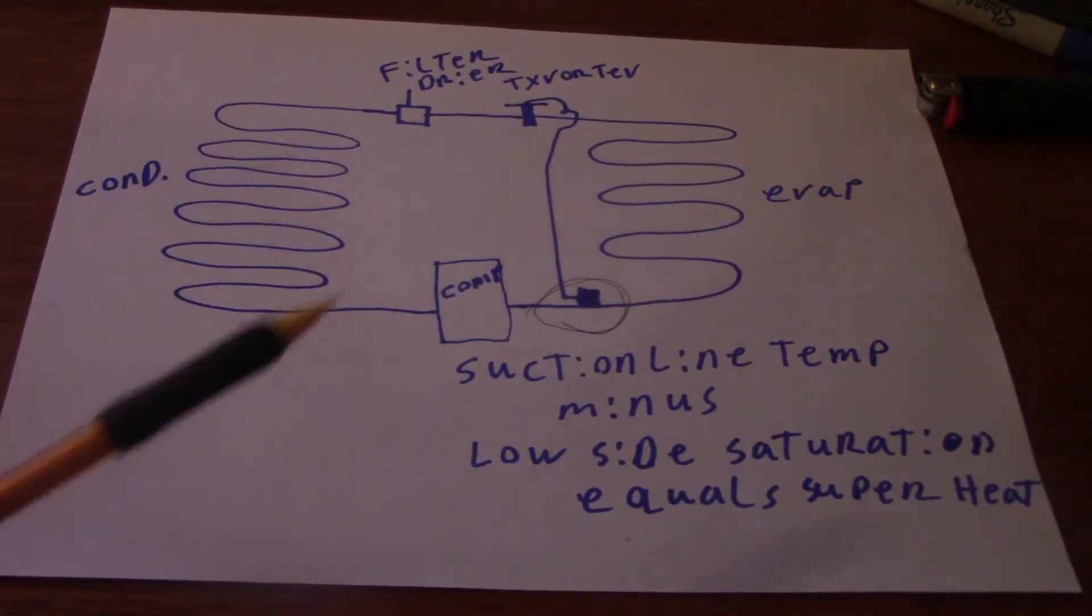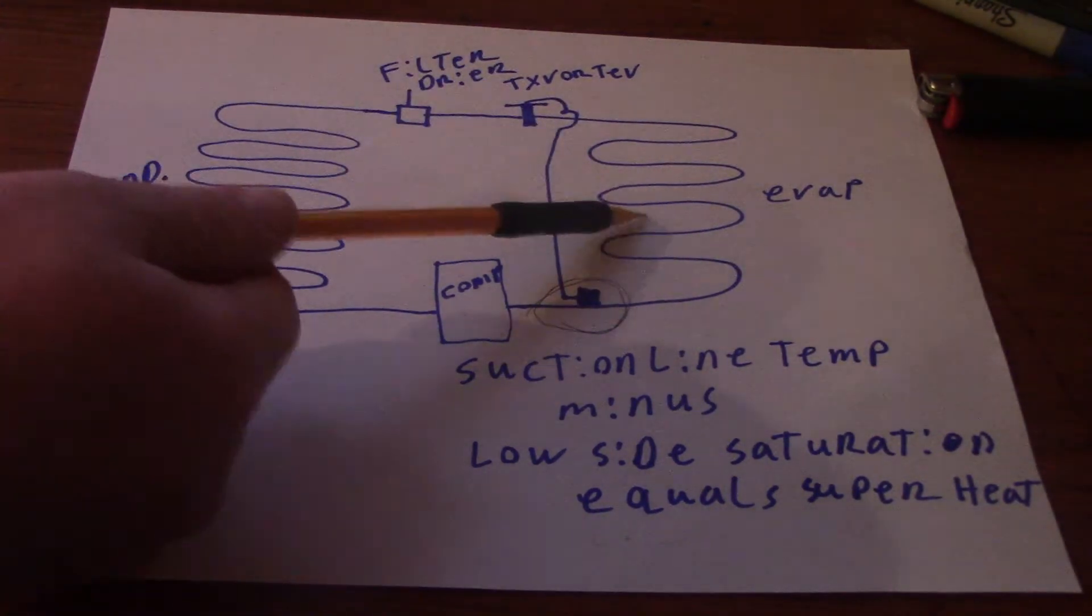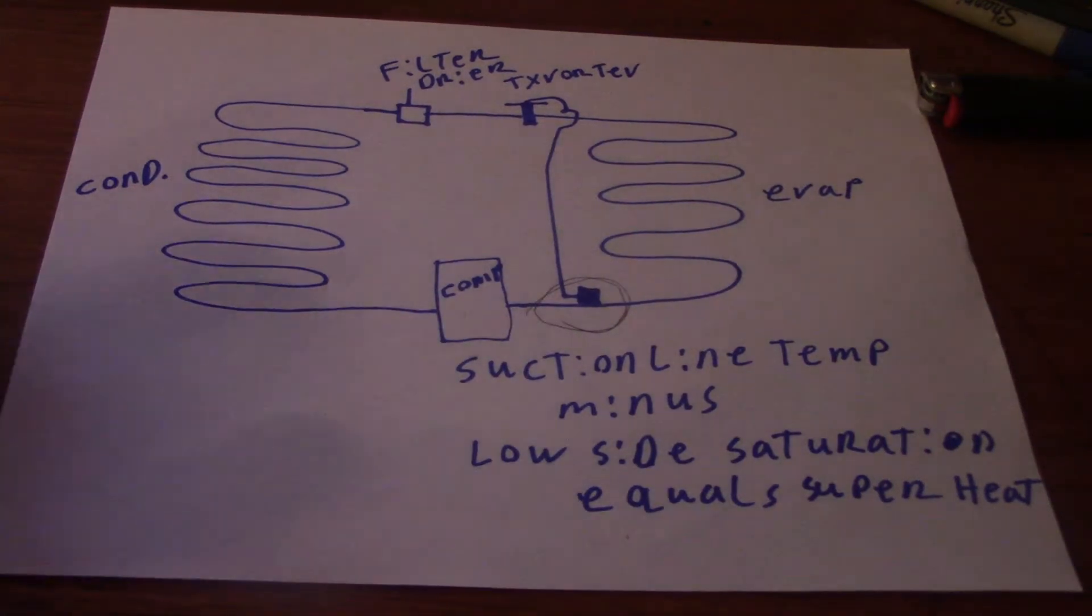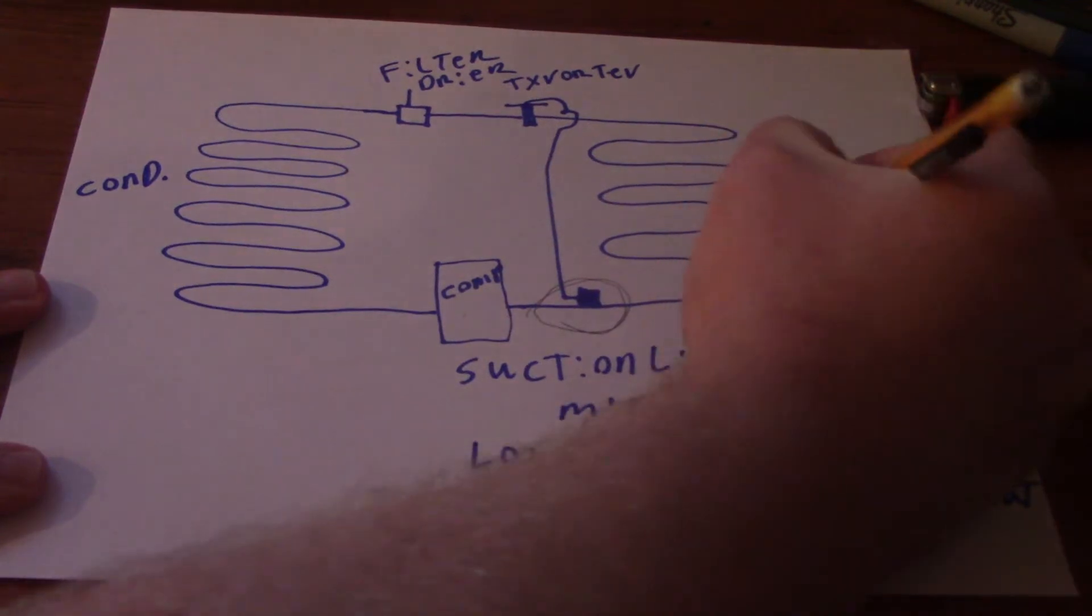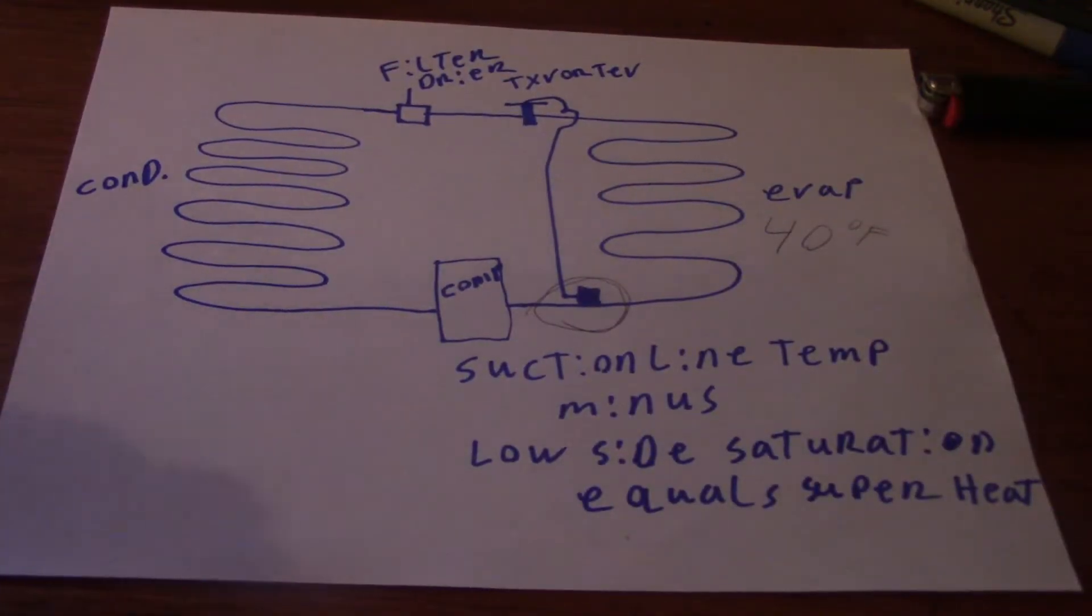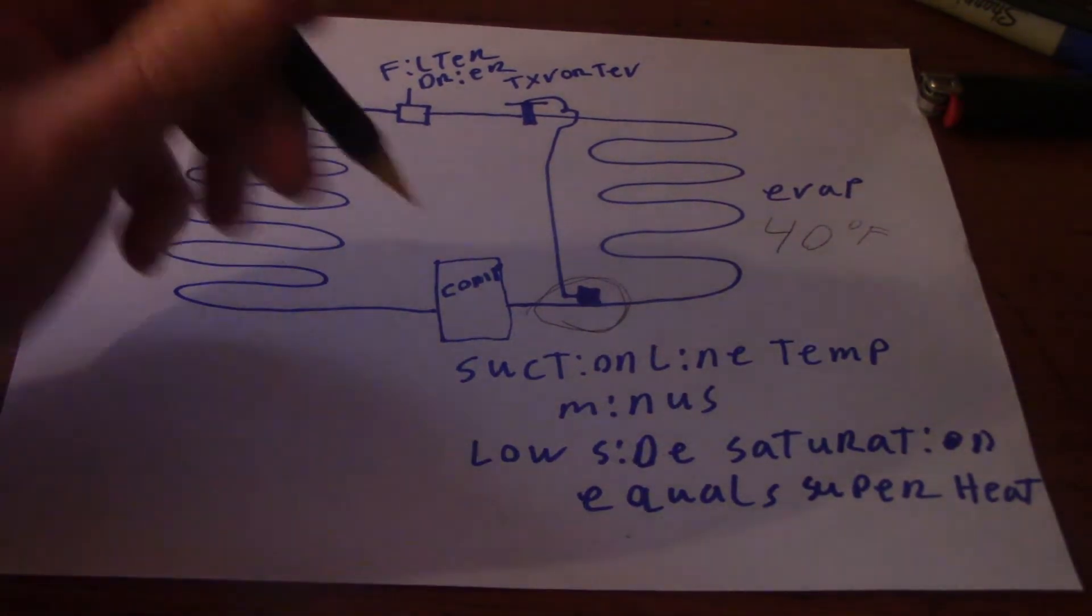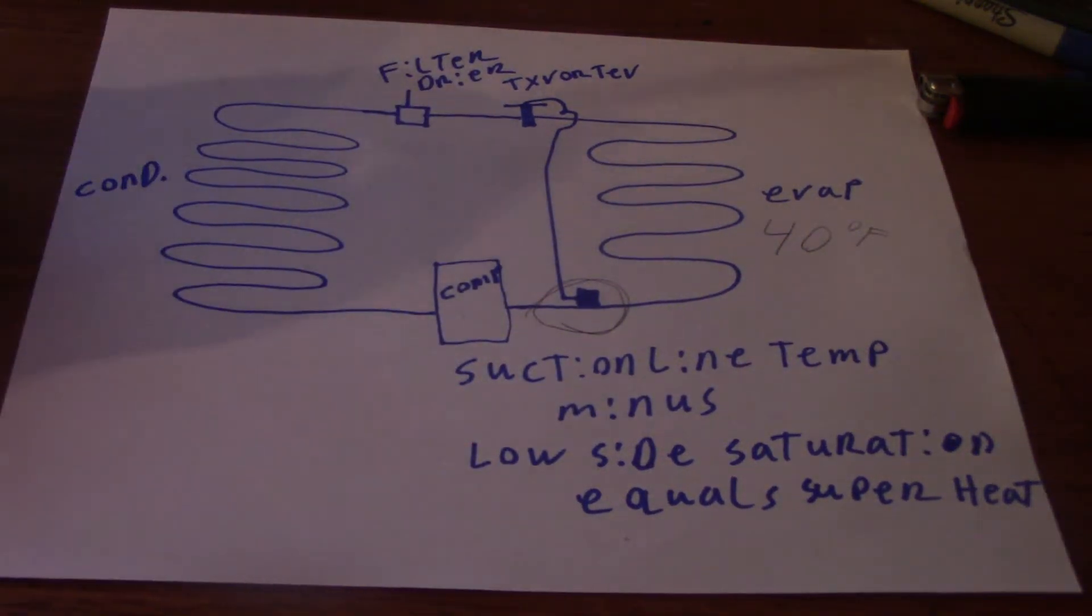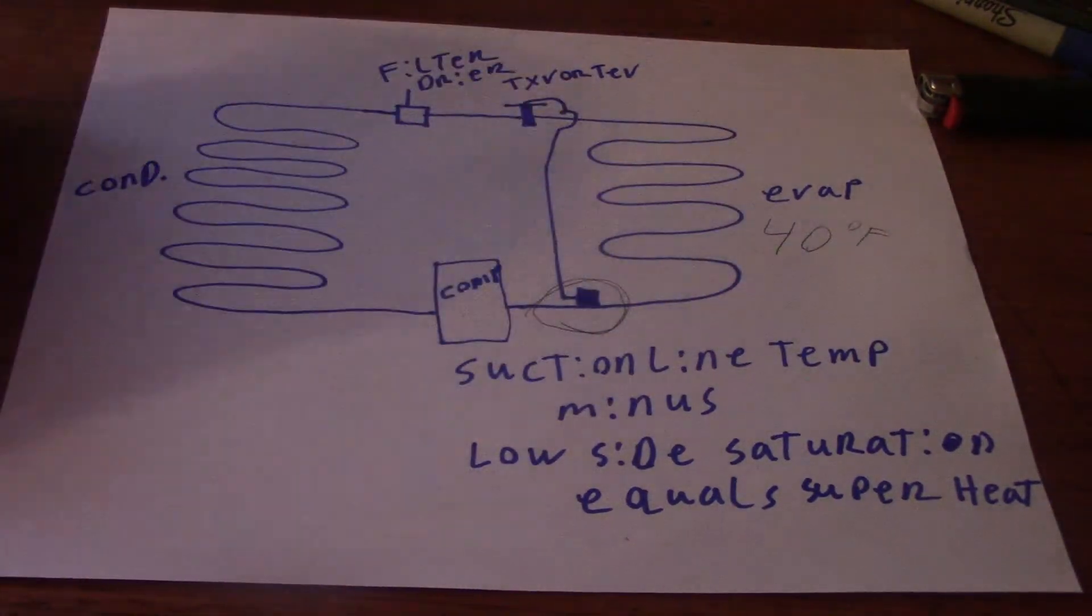All we're doing is checking if the evaporator here, we're going to pick, we'll say air conditioner. It boils off at 40 degrees Fahrenheit. That's going to be what's called the saturation temperature. You get that by taking your gauge, you hook it to the low side of the system. If it was R22, let's say 70 PSIG, 69, 70, you'd be looking at a 40 degree evaporator.